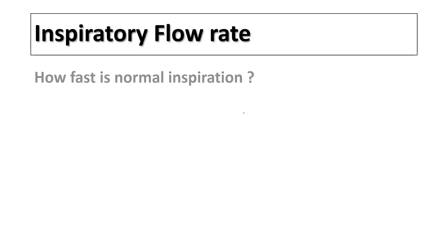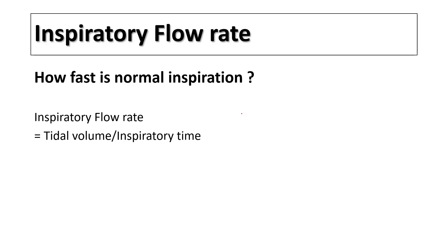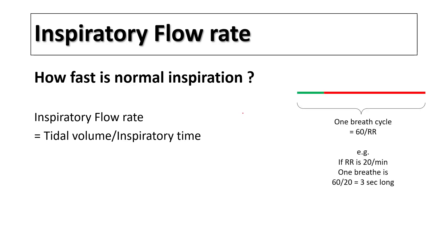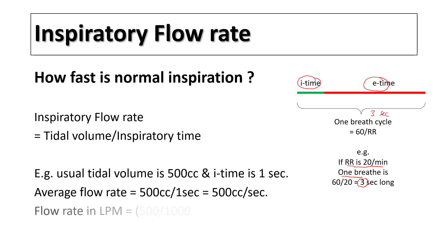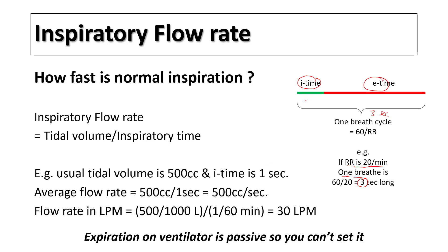Inspiratory flow rate is how fast you take the tidal volume, so inspiratory flow rate equals tidal volume divided by inspiratory time. This represents your breathing cycle, constituting your inspiratory time and your expiratory time. For example, if your breathing rate is 20 times a minute, your one breath cycle is around three seconds long. If your tidal volume is 500 cc and your inspiratory time is one second, the average flow rate would be around 500 cc per second, or about 30 liters per minute. Expiration on the ventilator is passive, so you cannot set it.